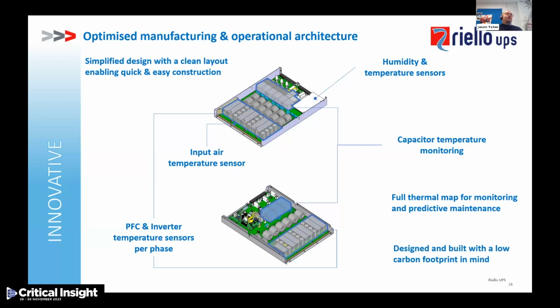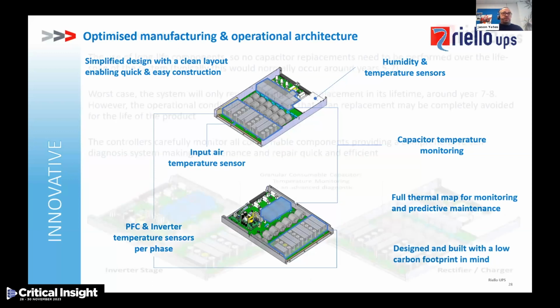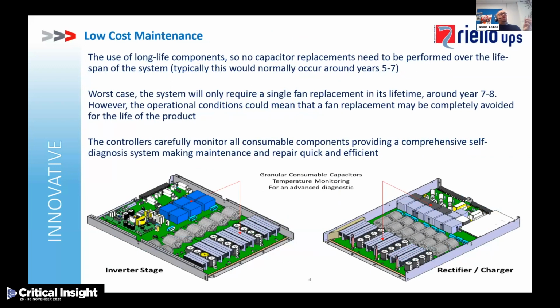So in terms of not just the energy and the optimization, we've got to look at the maintenance costs. Now, we've used long life components in these systems. So effectively, there are no capacitor replacements required over the lifespan of the system, which would typically be 15 years. Now, normally what would happen is every 5 or 7 years, a traditional UPS system would require a fan and a capacitor change, let's say year 5 or year 7. So over a 15-year life, a traditional UPS would have the capacitors changed at year 5, then again at year 10. So obviously there's a cost to that.